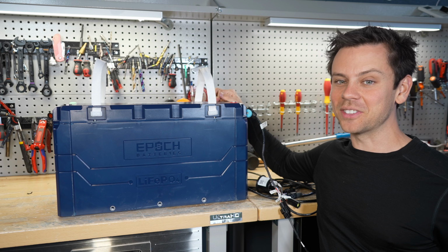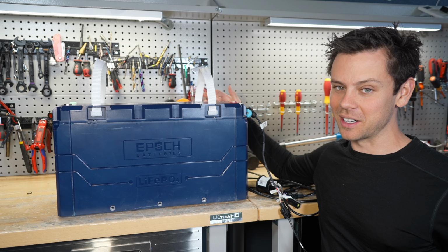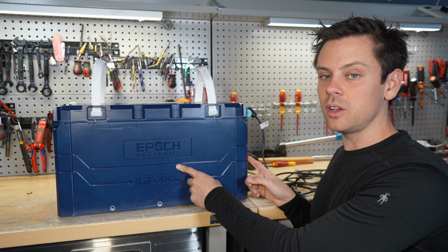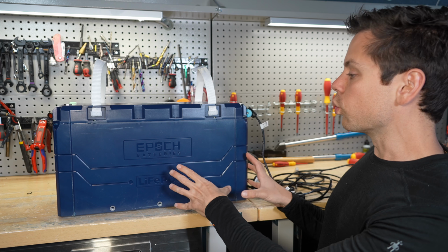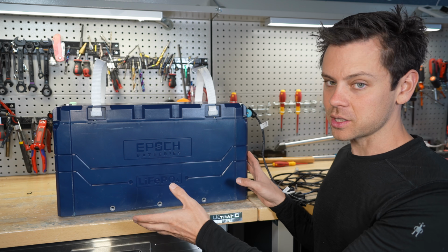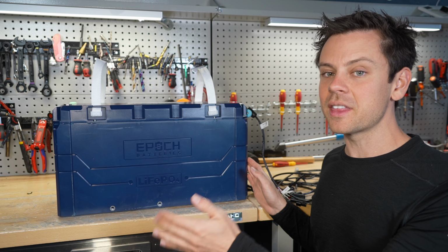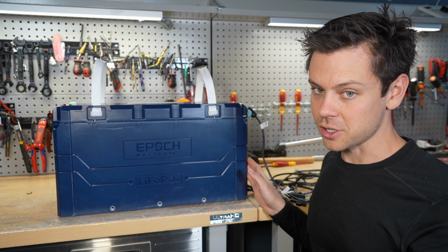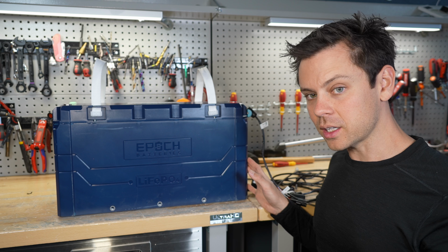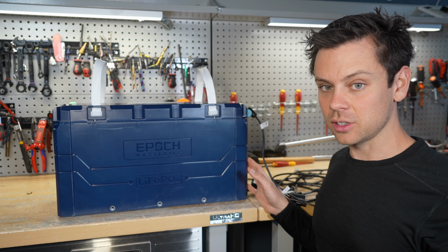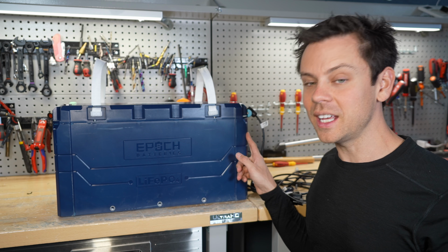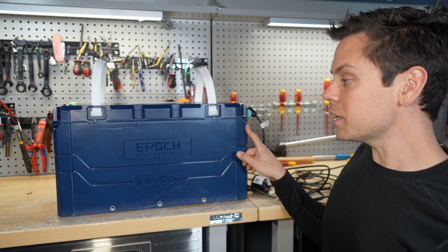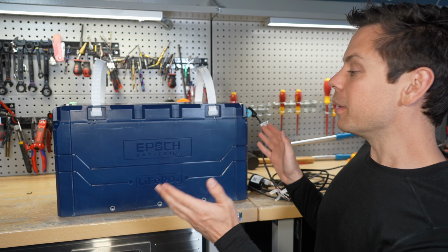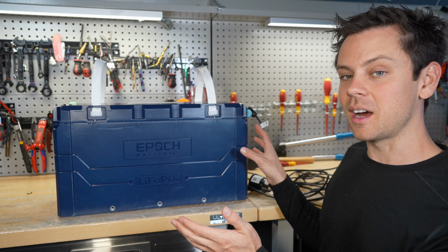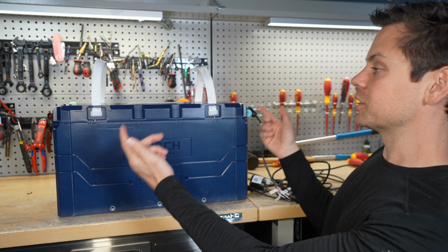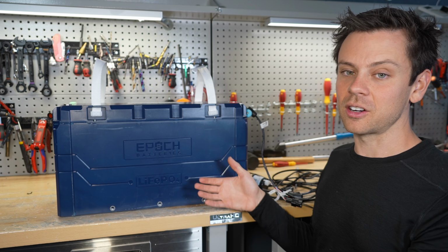Next, the T-class fuse is expensive and you need to have spares. Next, the internal heaters worked well and it only took 8 amp hours to warm up this entire battery pack from frozen. But with any lithium iron phosphate battery, they can discharge to a lower temperature. So if you want to warm up a battery quickly, discharge it with a large load and you'll see the temperature rise quickly and then you can charge it. Because warming up this battery took almost an hour. But the heaters worked as advertised. They did not pull from the batteries, they pulled from the terminals, it warmed up and then it started charging.